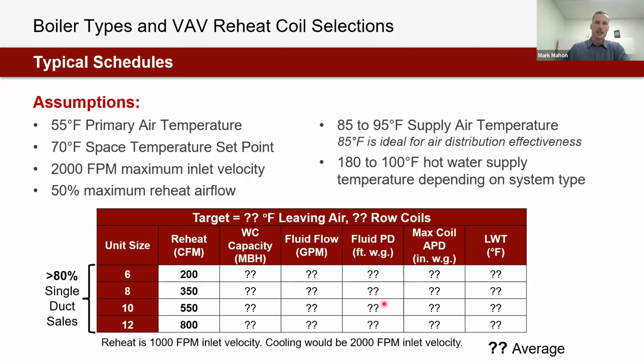And 2,000 feet per minute is an important number because above 2,000 feet per minute, airflow has self-generating noise as it moves through a ducted system. What we're going to see is airflow becomes so turbulent, it moves above a certain Reynolds number threshold, that air pressure drop starts to get out of control, acoustics start to get out of control, and airflow measurement and control can be influenced and impacted in some respects as well. So 2,000 feet per minute is an important number.